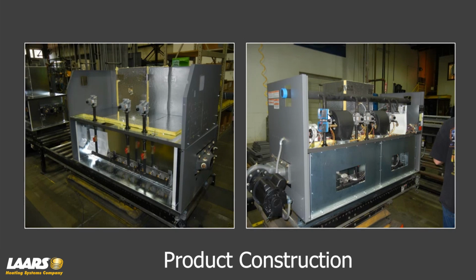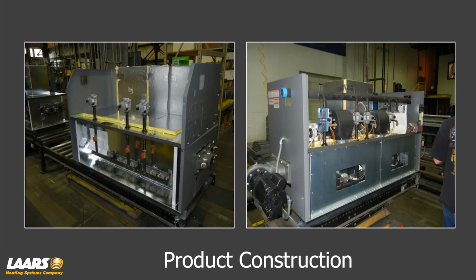Next, they're going to add CSD1 controls if it's a CSD1 boiler. My example here is a low gas pressure switch and a high gas pressure switch. They'll add the cover plate for that chamber. I referred to this as a plenum. And then we'll have two little sub panels. What are those sub panels? We use hot surface igniters on these. So instead of having to pull off the whole cover, it's simply 6 screws, and you can gain access to your igniter if you need it.